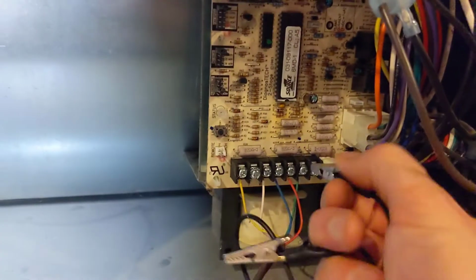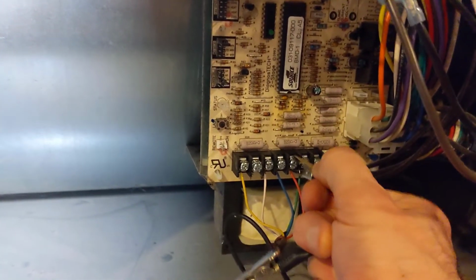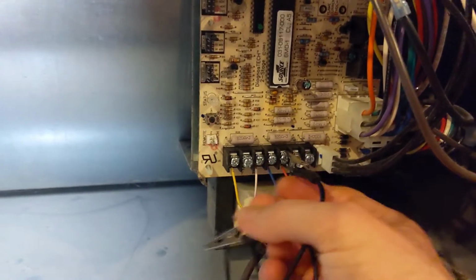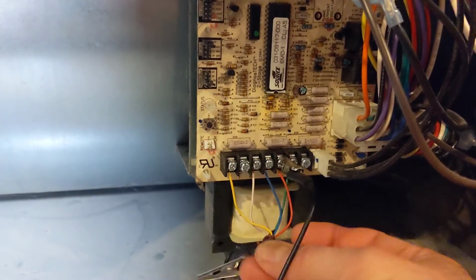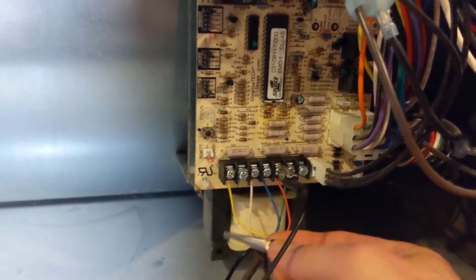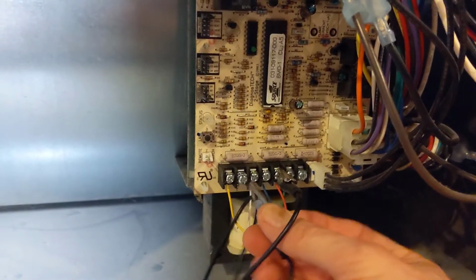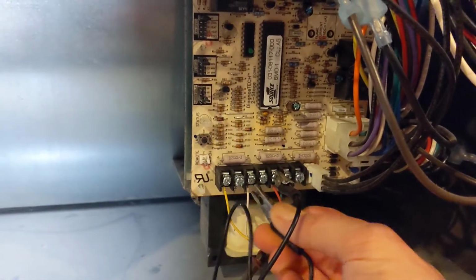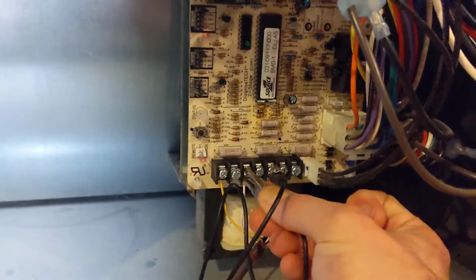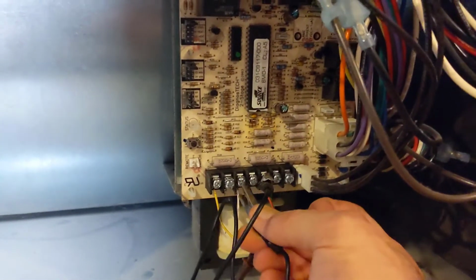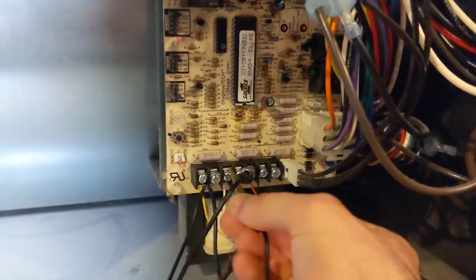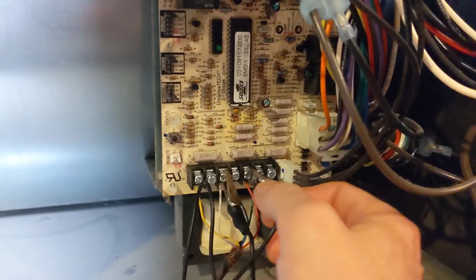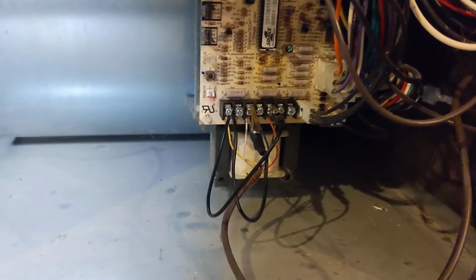Okay, so I turn the furnace off. Let's go ahead and get our jumper. Always turn the furnace off before you jump it out, just to make sure your jumper doesn't short out, because if this falls against sheet metal, then that red wire will ground out. So trying to do this one-handed here. It's not very easy. Okay, so now that that's secure, let's go ahead and turn it on and we'll watch the operation.